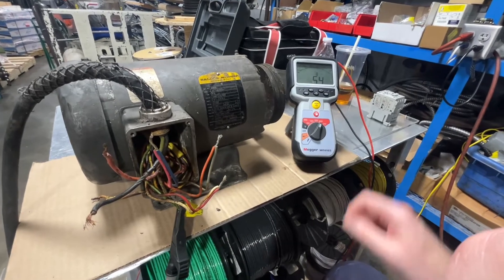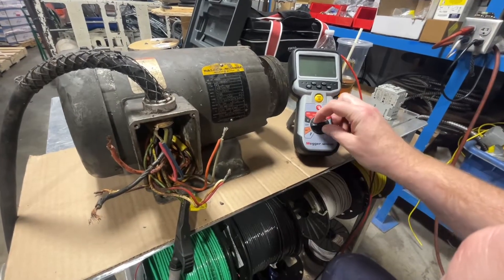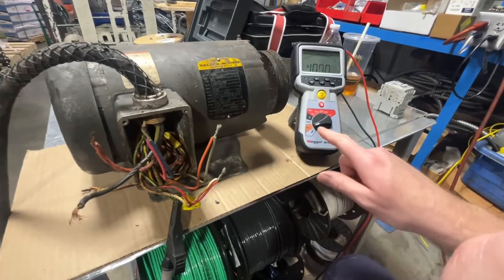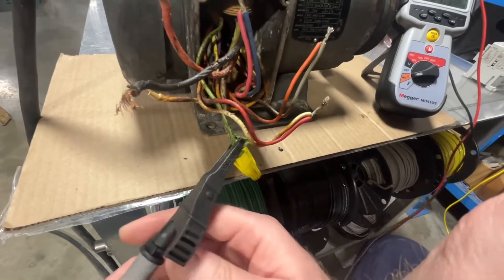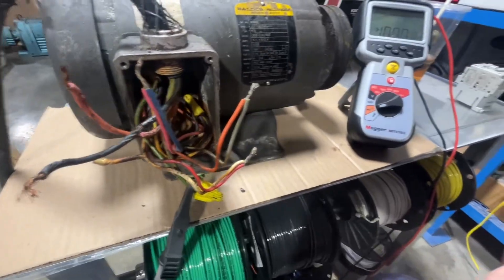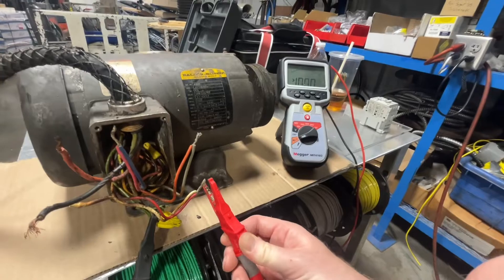Here we have a Baldor motor, a one-half horsepower motor. We're going to be doing a resistance test to ground. I've got the meter set on resistance mode. We're going to put the black lead on the green conductor — the insulation is stripped back so it's a good connection — and we're going to start reading these windings to the ground, or the frame of the motor.